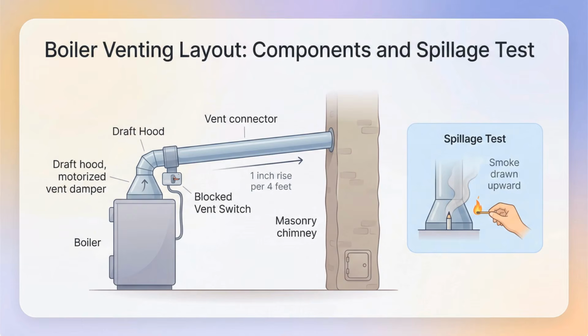After venting is installed, a spillage test is performed. Run the main burner at least 5 minutes, then use a match, candle, or smoke tester at the draft hood entrance. The flame or smoke should be pulled into the draft. If it spills out, something's wrong.